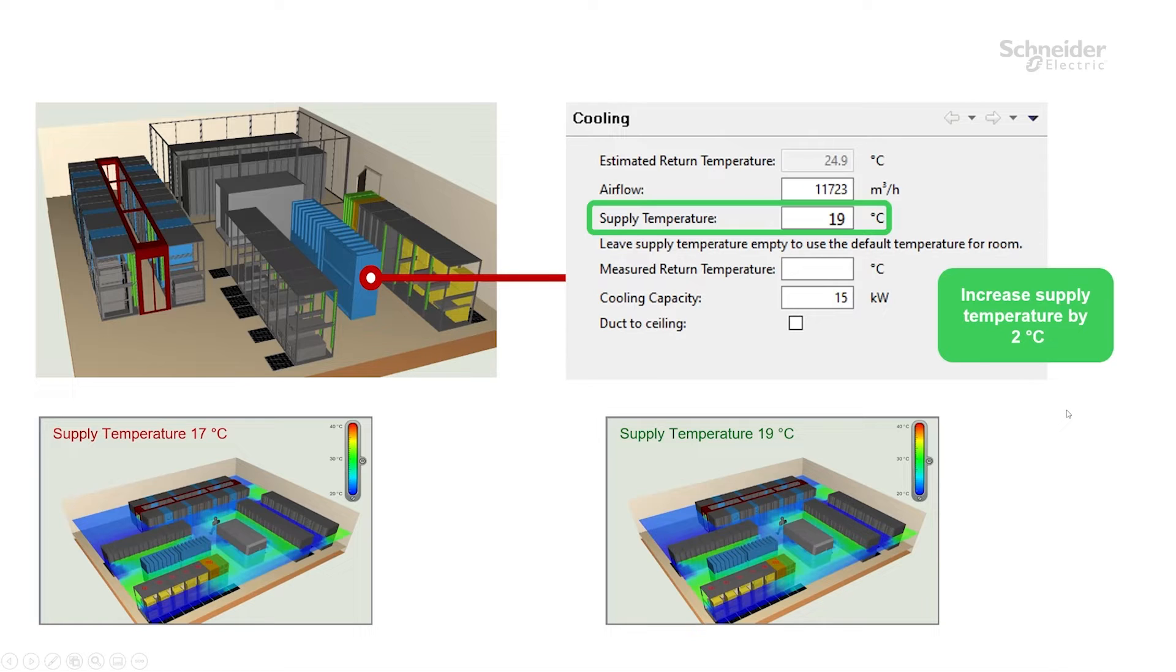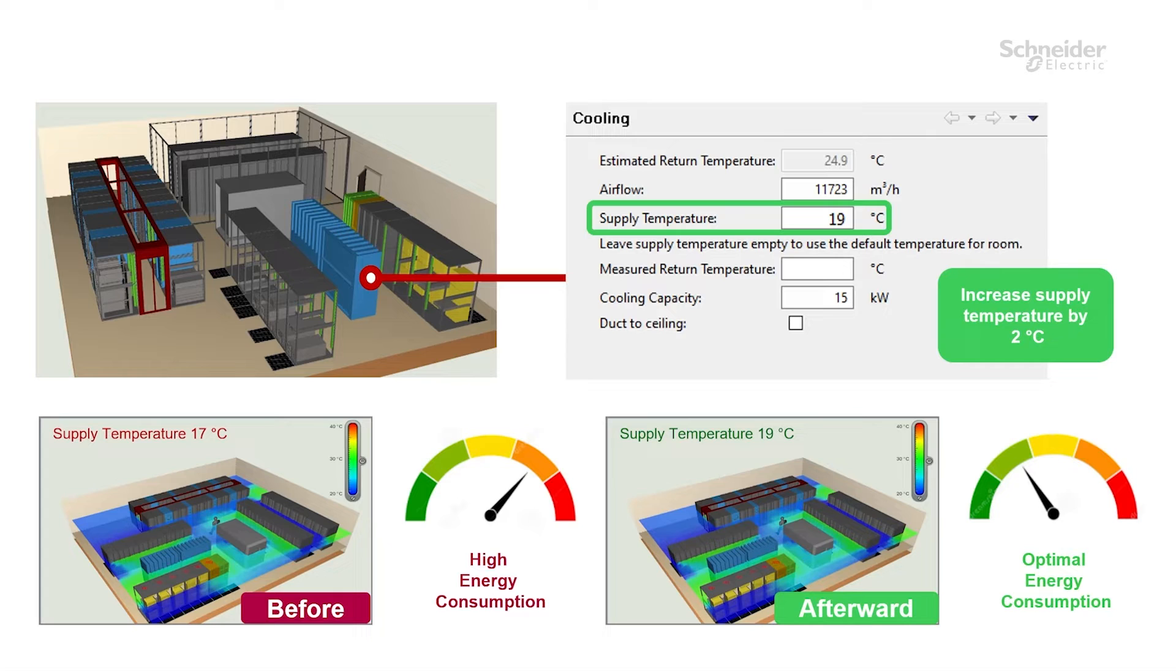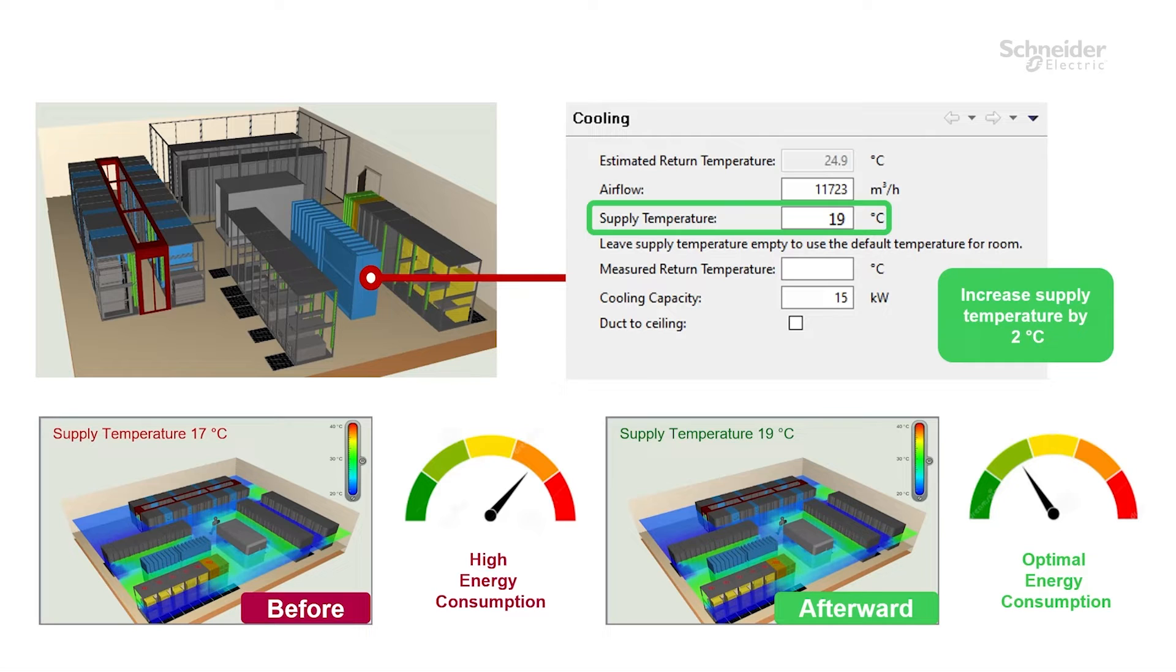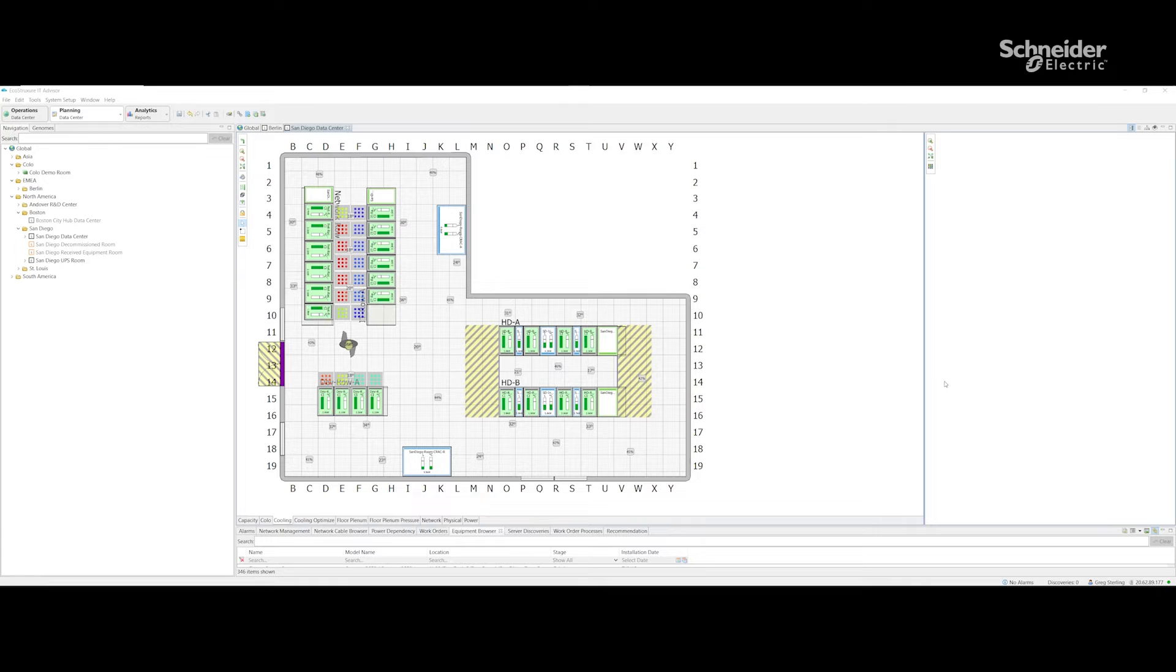But from the perspective of energy consumption we are going to quickly discover that we have far lower energy consumption if we use supply temperature 19 degrees. Every degree is going to help us save energy. Now let's have a look at examples inside IT Advisor and see how this could be achieved inside our infrastructure IT Advisor tool.